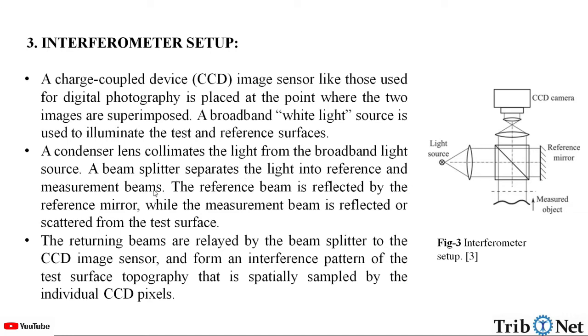The reference beam is reflected by the reference mirror, while the measurement beam is reflected or scattered from the test surface. The returning beams are relayed by the beam splitter to the CCD image sensor and form an interference pattern of the test surface topography that is spatially sampled by the individual CCD pixels. Here in the figure, we can see the components making up the interferometer setup.